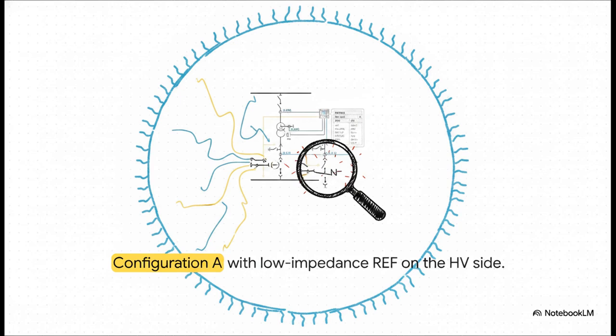To picture this in action, think about configuration A on the high voltage side. The relay is taking inputs from both the phase CTs and the neutral CTs. It's basically acting like a magnifying glass, zooming in specifically on that neutral point, because that is exactly where a small fault is most likely to hide from your broader protections.